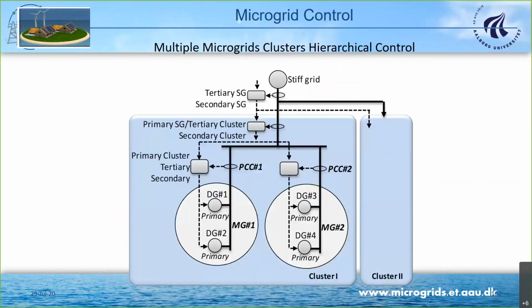If we are able to integrate a hierarchical control system for a single microgrid, like the primary, secondary, and tertiary, we will also be able to interconnect a number of microgrids in parallel, forming what we call multiple microgrid clusters. This means that on top of the primary, secondary, and tertiary control levels of my microgrid, I can create a primary level for my cluster of microgrids. So there will be distributed control of the different microgrids, another level to restore voltage and frequency in my cluster of microgrids, and finally the tertiary level to handle a number of clusters of microgrids and balance the power flow between them.